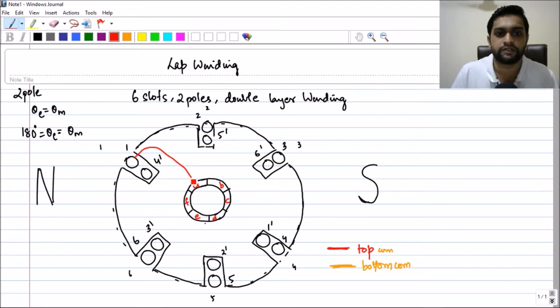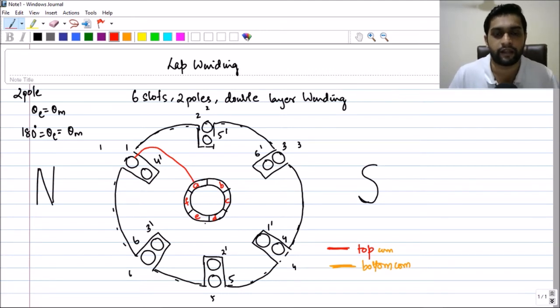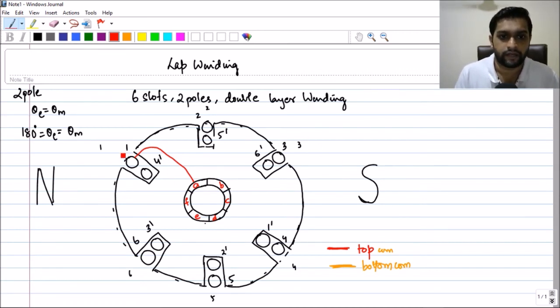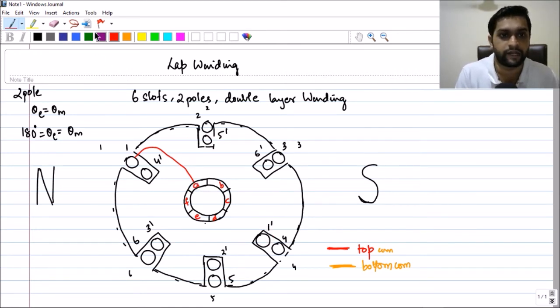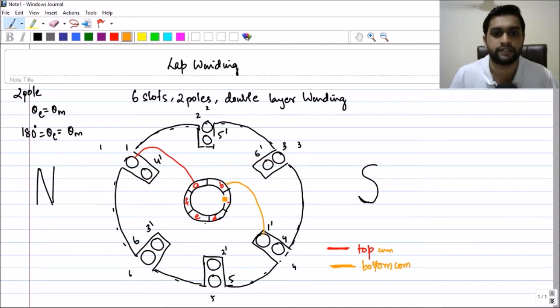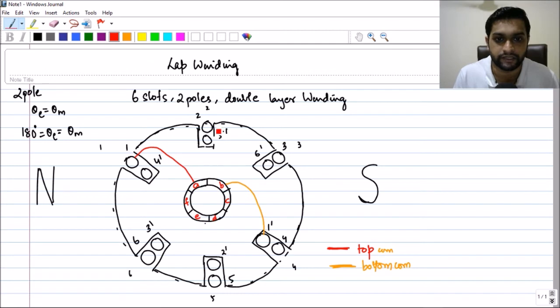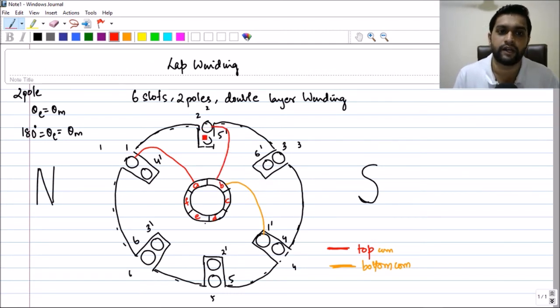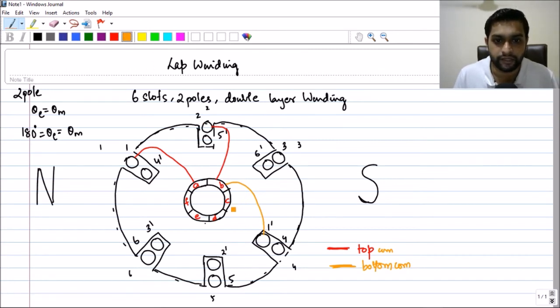Conductor one is connected to commutator A — it's a top connection so I use a red line. The other end of coil one, which is one-dash, is connected to the next commutator B. So one-dash and two are connected through commutator B. Now two-dash will be connected to the next commutator — since two is connected to B, two-dash will be connected to C, using a yellow line for the bottom connection.